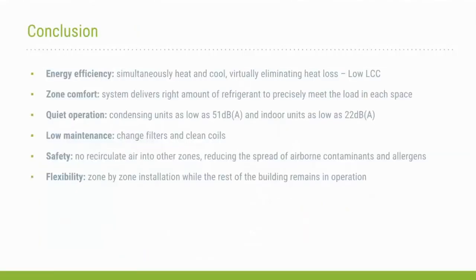And really to conclude is that they have an obvious energy efficiency, and we do use them for simultaneous heating and cooling, not to miss that point, but the courthouse, because of the type of occupancy it is, actually has a need to heat one space while cooling another, so we're able to use that inherent simultaneous heating and cooling situation that a VRF gives us to drop our energy costs. At the same time, it actually makes the zones more comfortable for our tenants, so there's a good payoff there. Our units are very quiet. They have a quiet operation. And it's actually fairly low maintenance. They really just change the filters and clean the coils on them.